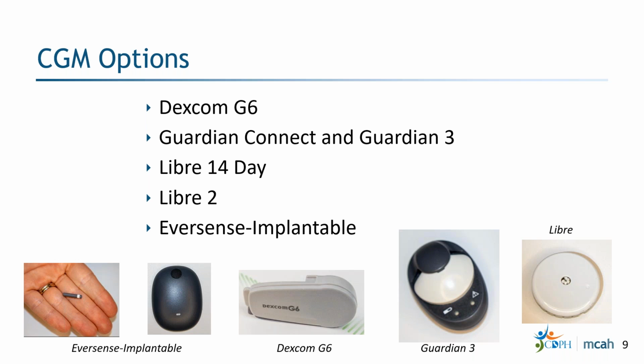To the right of the G6, we have the Guardian Connect, as well as the Guardian 3. They look the same. The Guardian Connect is a standalone CGM that works with a smartphone, and the Guardian 3 works with the Medtronic insulin pumps. But what you see there is actually the transmitter on the charger. This transmitter is also attached to a sensor, and this transmitter is good for a year or longer, but it does need to be charged every week in between use.